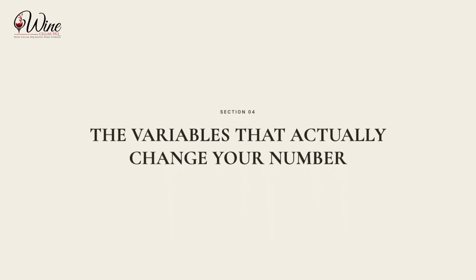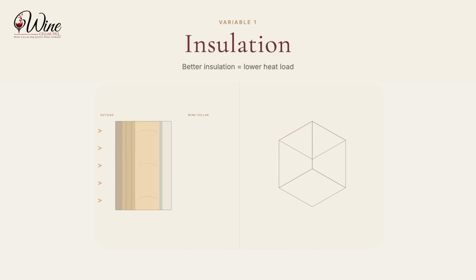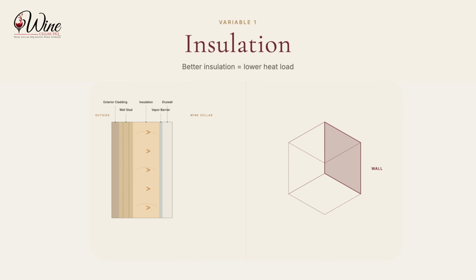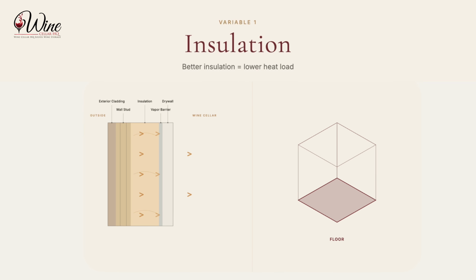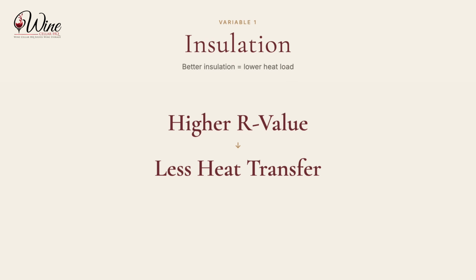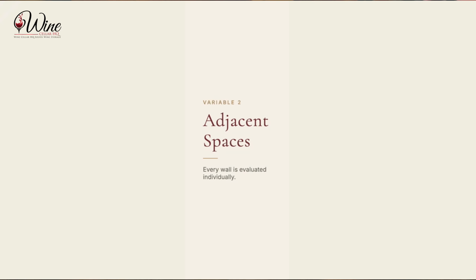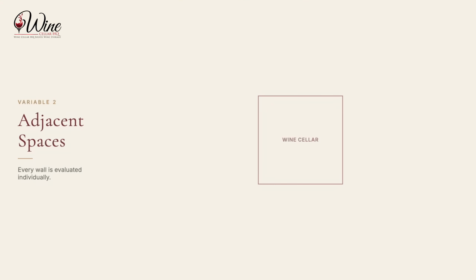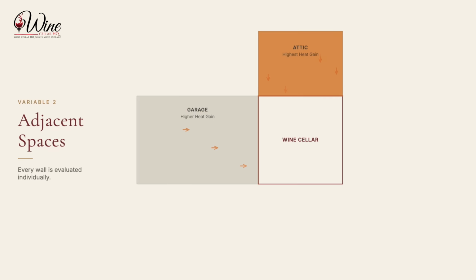So what actually goes into a real heat load calculation? Here's what a proper calculator is going to ask you for. Insulation. Every wall plus your ceiling and floor gets an R value. Better insulation, less heat getting through, simple as that. But it makes a bigger difference than most people expect. What's on the other side of each wall? A wall facing a cool conditioned basement barely adds to your load. The same size wall facing a hot garage or direct sun adds a lot. Every wall gets looked at individually.